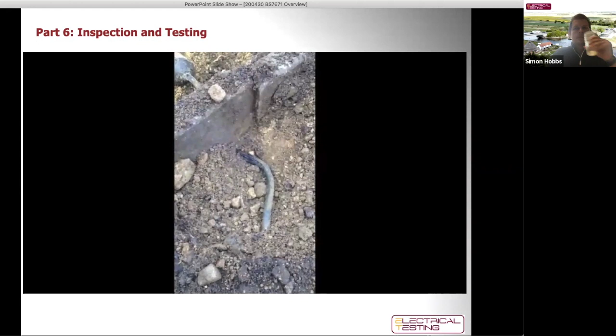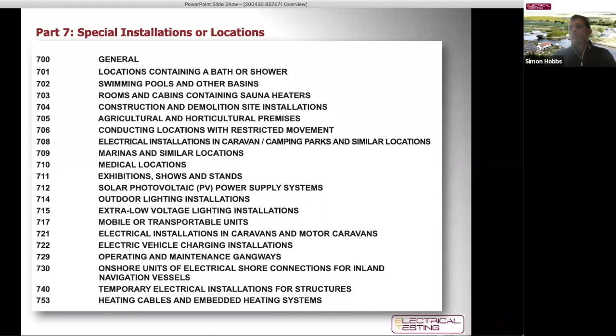We move on to part 7, the last part of the regulations apart from the appendices: special installations or locations. We're looking at things like caravans, caravan parks, street lighting, outdoor lighting, marinas, swimming pools, bathrooms, EV charging for electric vehicles, and so on. There's a fairly long list of special installations or locations. The main thing with regards to these installations is that they generally have an increased risk of electric shock or fire, or some other increased risk related to electricity. So what we find with part 7 is that it provides additional safety precautions for those particular installations.